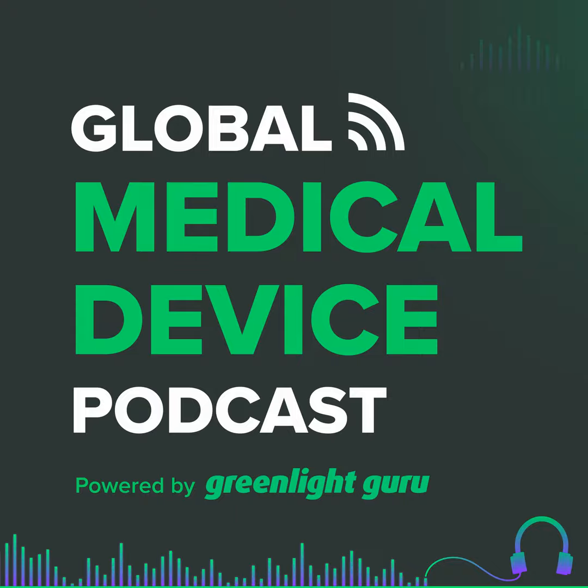If you're going to do a clinical trial for your NSR device and you don't tell FDA about it first, and again, you have no obligation to, and you spring it on them for the first time at the point of the submission, then be prepared for them coming back and saying, well, what about this other endpoint? You didn't measure this endpoint. We would like to see that. So now you may have to do a whole clinical trial over again in order to collect that information. Ka-ching, ka-ching, ka-ching. It's a calculated risk.